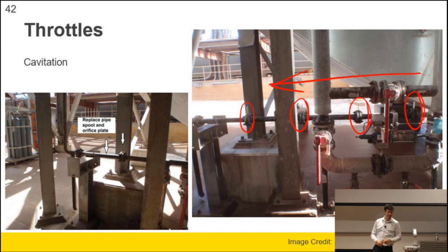Yeah, there was a bunch of stuff about the system I wanted to do and applied for capital to say, really, this is the best we can do: run a pump 24/7 and just push it through an orifice. But yeah, that was what you had. This was a job called maintaining what was there, because the cavitation was wearing that out every 6 months. So that was a problem. Yeah, the capital was to change the system. That's that. Yeah, go, Chris.